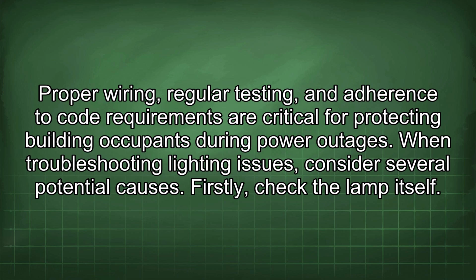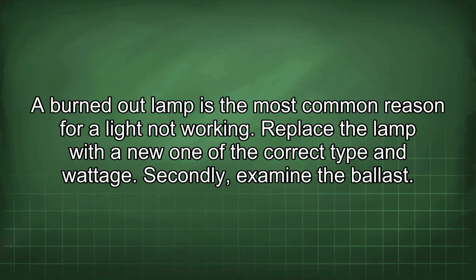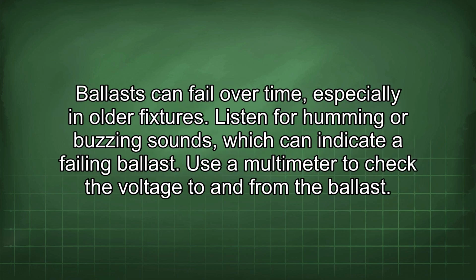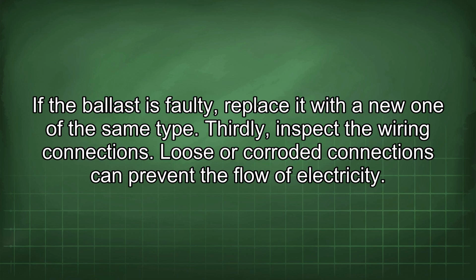Firstly, check the lamp itself. A burned-out lamp is the most common reason for a light not working. Replace the lamp with a new one of the correct type and wattage. Secondly, examine the ballast. Ballast can fail over time, especially in older fixtures. Listen for humming or buzzing sounds, which can indicate a failing ballast. Use a multimeter to check the voltage to and from the ballast. If the ballast is faulty, replace it with a new one of the same type.